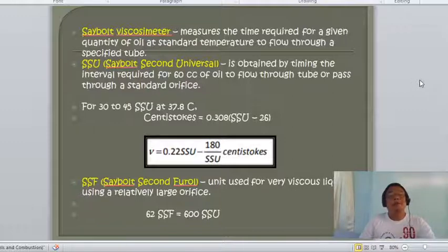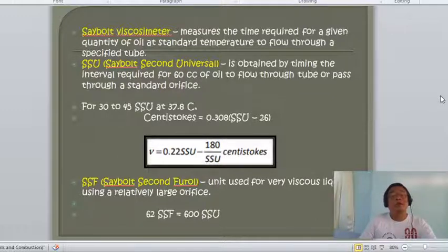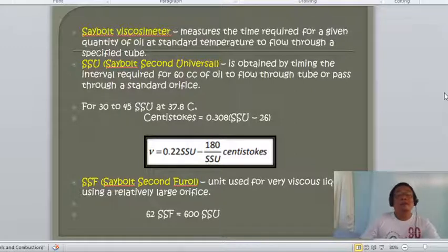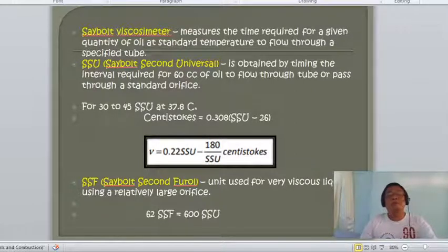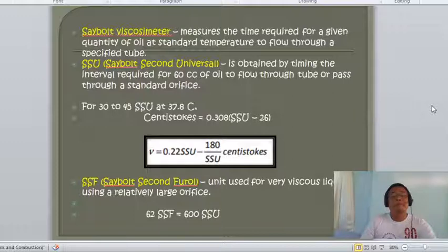For conversion to centistokes: centistokes = 0.308 × (SSU − 26), or viscosity = 0.22 × SSU − 180/SSU. We also have the SSF (Saybolt Second Furol), a unit used for very viscous liquids. Another conversion: 62 SSF equals 600 SSU.